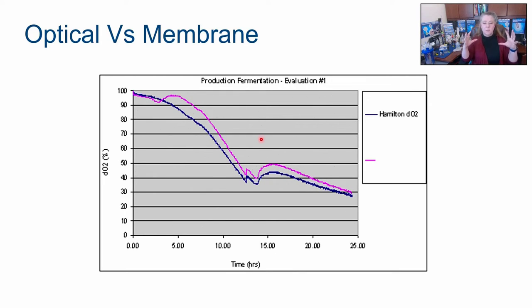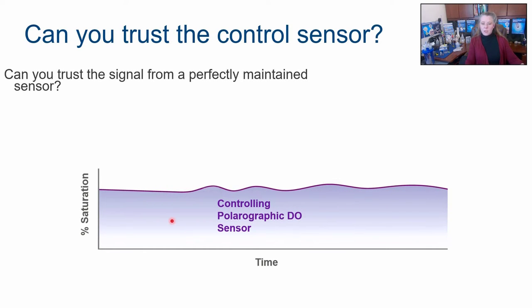And if your system is super sensitive to oxygen, a 5 to 10% deviation in oxygen could end up with a huge difference in the viability of your population, in how much product comes out at the end, all of that. Okay. So how do you know if you can trust the control of your sensor? Here's another example. We're going to put two sensors in a tank, polarographic and optical. We're going to control the oxygen off the polarographic, and we're going to run this for about 2 weeks. We're just going to monitor with the optical. In theory, they should be the same.